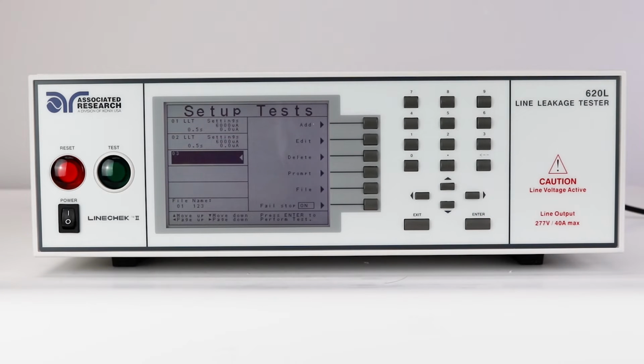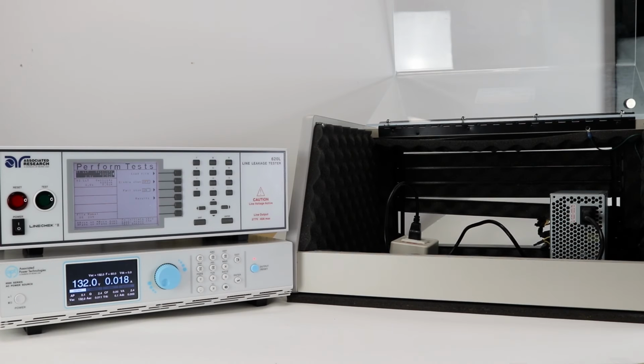In the video, we have set up an earth leakage current test under normal conditions, followed by an earth leakage current test with an output neutral fault. We will be using the IEC 60950-1 measuring device. Next, we're going to connect an external power source to the linechek. This will allow you to run power through the linechek to power up the DUT during the line leakage testing. Then, we'll connect the linechek to the DUT and run a test sequence.